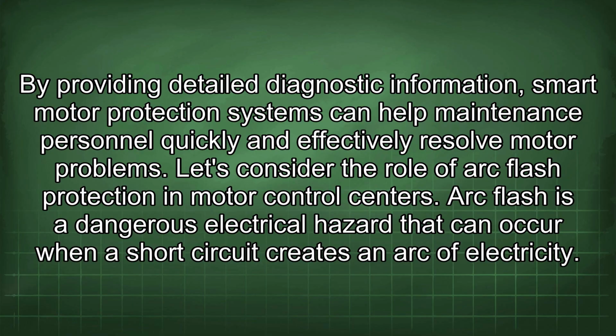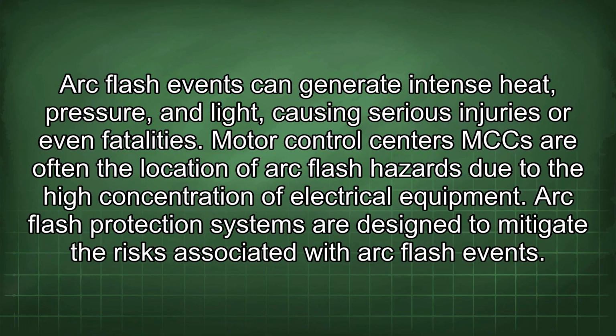Let's consider the role of arc flash protection in motor control centers. Arc flash is a dangerous electrical hazard that can occur when a short circuit creates an arc of electricity. Arc flash events can generate intense heat, pressure, and light, causing serious injuries or even fatalities. Motor control centers (MCC) are often the location of arc flash hazards due to the high concentration of electrical equipment.